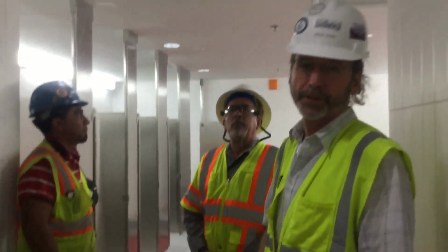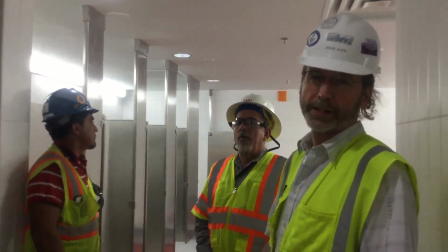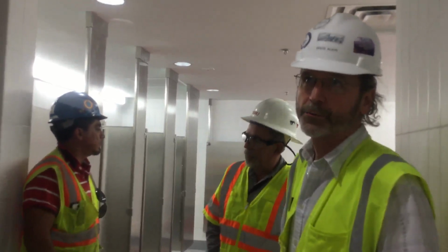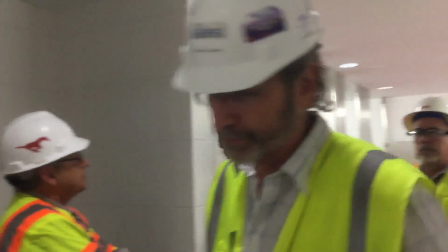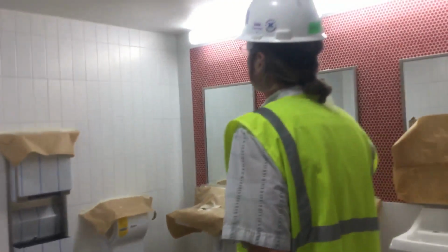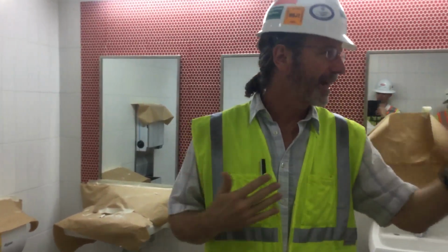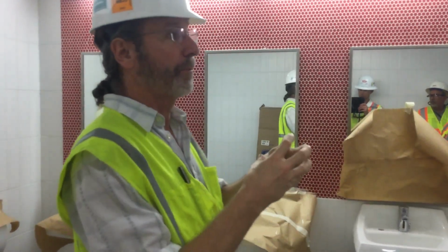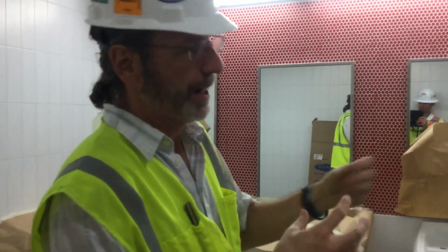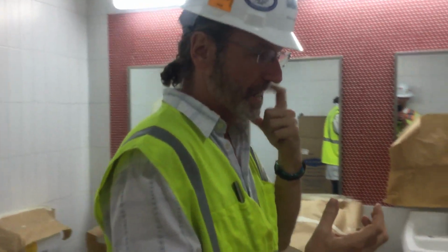Now here's the last example of a ceiling mounted occupancy sensor in a space. We're in the restrooms right now, and up on the ceiling we have some small 24-volt sensors. Right here, an ultrasonic occupancy sensor. There's another one on the other side of the restroom. They're wired together and come back to a 24-volt power pack, which acts like a power supply and relay.